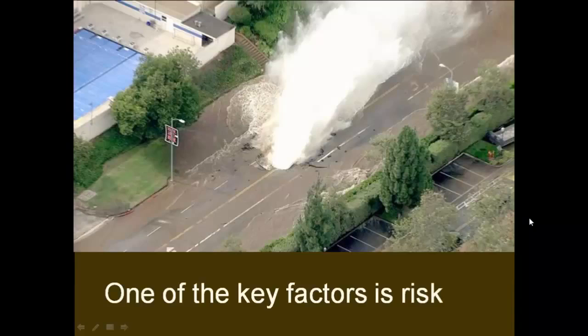It was a high pressure pipe, so the probability of failure would be a little higher. It was a pipe that had shown some deterioration. So there were a lot of reasons to believe that this particular pipe had a pretty high probability of failure, and it had a very high consequence of failure because a lot of water could escape, it was close to the college campus, and the water would flow downhill into other structures. So this particular pipe would have ranked pretty high in terms of criticality. Based on the rest of their network, they have about 7,200 miles of pipe in their system. Comparatively with other parts of the system, I can't say, but certainly it would be a very high consequence pipe or high risk pipe.